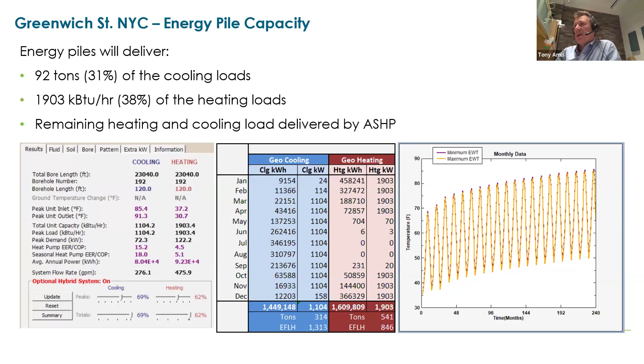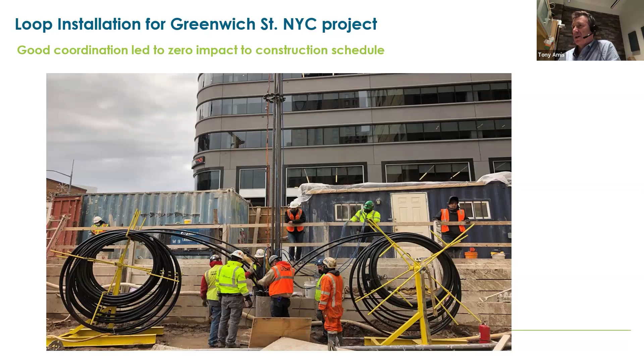But also the important thing is to work out how much of the heating and cooling the foundations can deliver. On this particular project, we were delivering over 30% of the building's cooling and about 40% of the building's heating. We combine ground source heat pumps here with air source heat pumps in this particular solution, which makes for a great hybrid solution. We can use those air source heat pumps to help moderate that gradient if necessary over time. And again, good coordination on this particular project: absolutely no impact on the construction schedule.